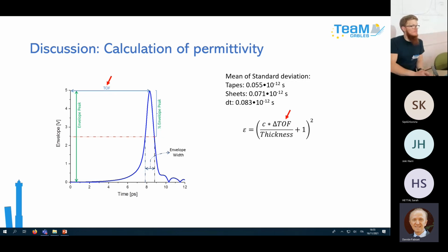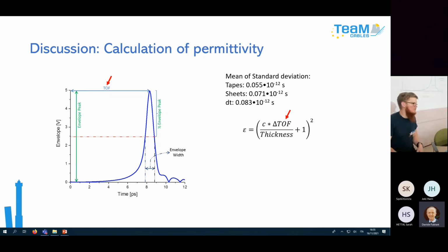When you work on the cable, are you in transmission mode or reflection? Reflection mode. It's not possible through the copper. Yeah, exactly. And that is also why we removed the outer jacket and the copper mesh, right? Okay. But it was said before in the presentation, of course, this is not practical in the usual case if you're thinking about containment, right? You can't go willy-nilly into a power plant and cut up the cables and remove the outer jacket.